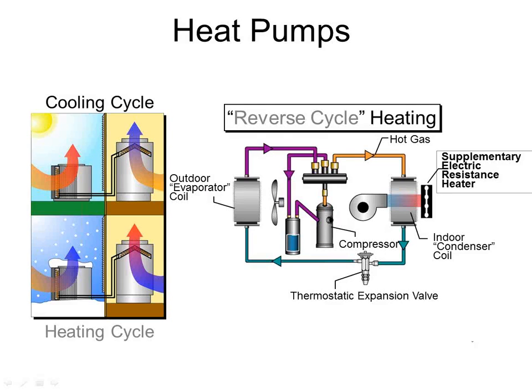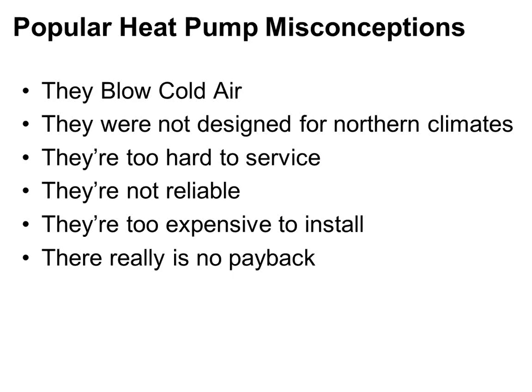Another common misconception is that heat pumps are not designed and can't be used in northern climates. That's absolutely not true. You're not going to use it in the Arctic, where it's always negative 10 degrees. But anytime I have mild conditions, meaning 20, 30, 40 degrees outside, I can use the heat pump. And in the Midwest, we always have days like that. In fact, I'll show you exactly how many we have. Another complaint is that they're too hard to service, right? Service techs get confused. There's really only 2 extra components. There's a reversing valve and there's an accumulator just to kind of buffer the extra refrigerant that we have. That's really it. Everything else is really the same.